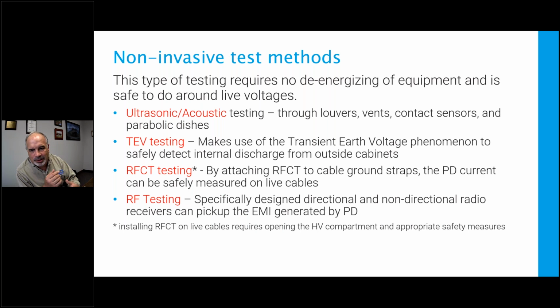Variety of different test techniques. So we've got acoustic testing, and that is ultrasonic or acoustic. But basically, I'm listening. I'm keeping the doors closed. I'm not connecting to anything. I have no direct connection to the power system. I'm listening through louvers and vents. I may use contact sensors. I may use a parabolic dish to look from the ground up to overhead assets. Clearly, that's non-invasive and is a great technique for finding any kind of surface discharge.